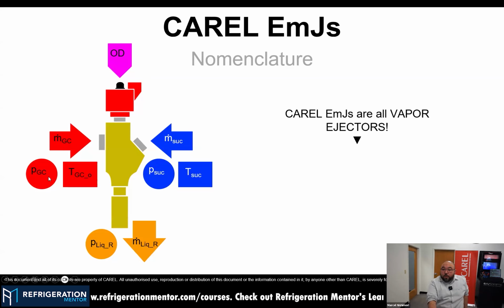We have the gas cooler pressure, the gas cooler outlet temperature that is defining, and the mass flow that comes from the gas cooler. Once we have a very high mass flow and a very high pressure, this expansion from the high pressure side to the liquid receiver causes what we call the Venturi effect, so a low pressure zone. So we are able to start dragging part or total refrigerant from the medium temperature line, so medium temperature pressure and suction, through the ejector and making a combination of that. So this is the very basic principle of the ejector operation conditions.